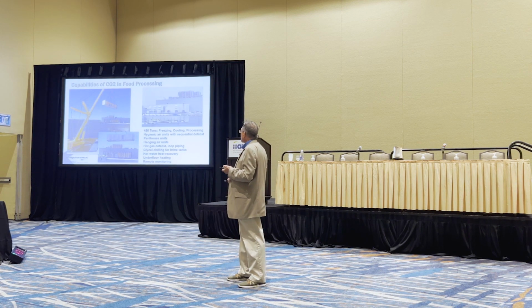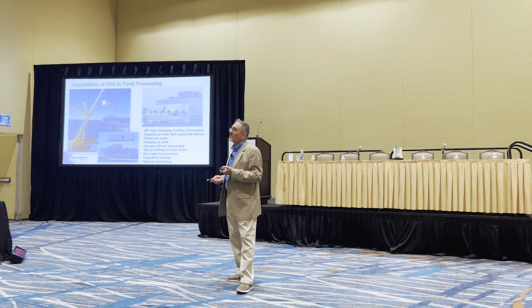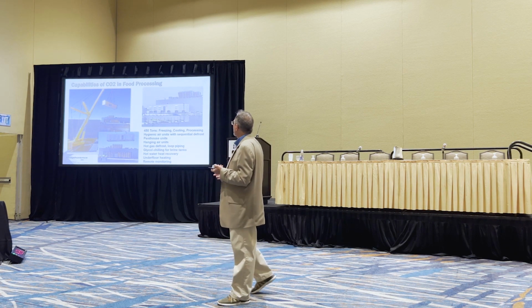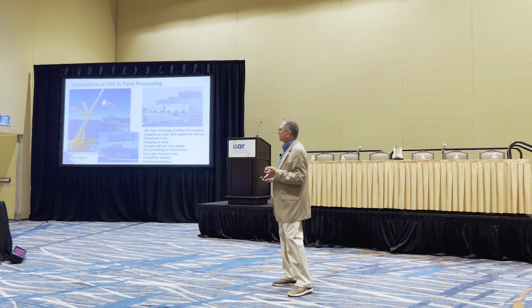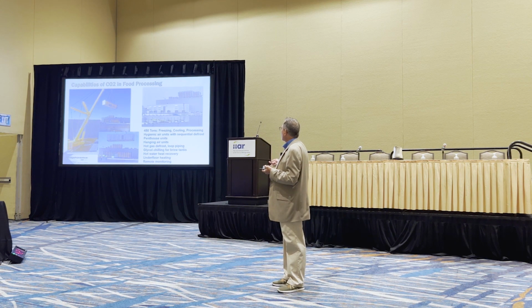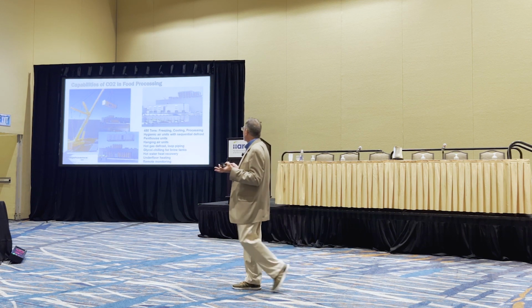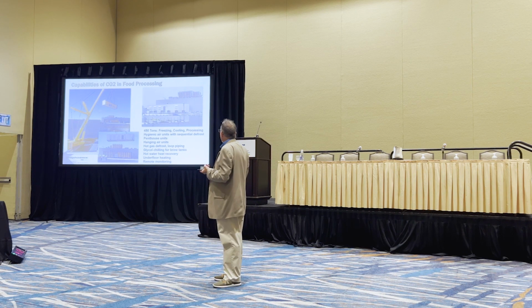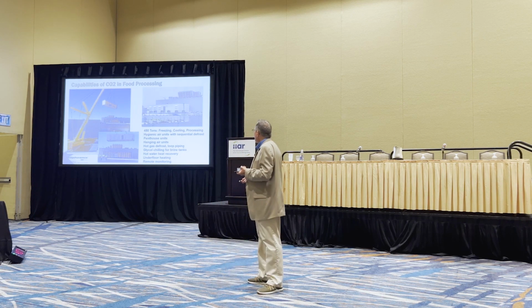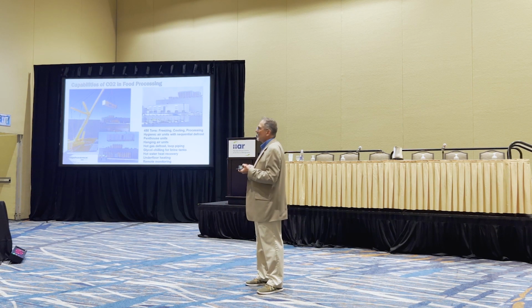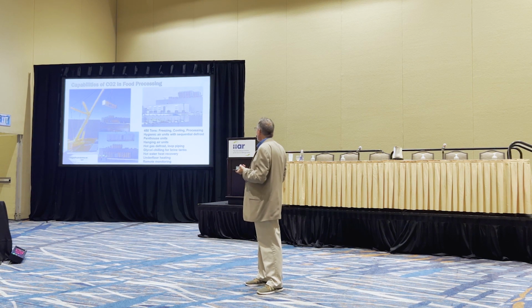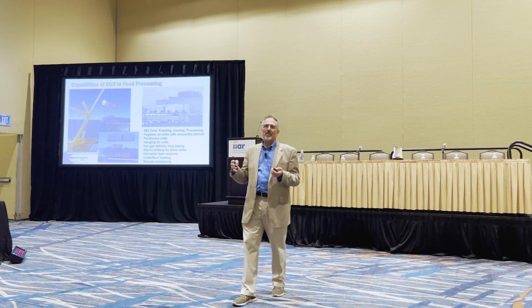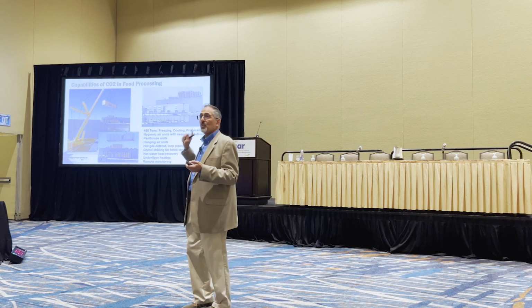Right? What we're seeing is a growing interest in applying CO2 in food processing. This is a particular food processor that we served in Pennsylvania. It's a meat processor, a turkey processor. It was 2 CO2 racks in side-by-side houses, put together to form what we call a mechanical room or a machine center. And 450 tons of freezing, cooling, processing, hygienic air units with sequential defrost, penthouses, hanging air units, hot gas defrost, loop piping, chilled water for brine tanks, hot water heat recovery, underfloor heat, just about everything you can think of that you otherwise would do in an ammonia system, you can do with CO2.